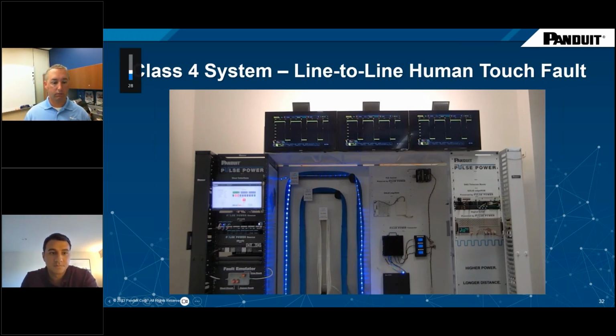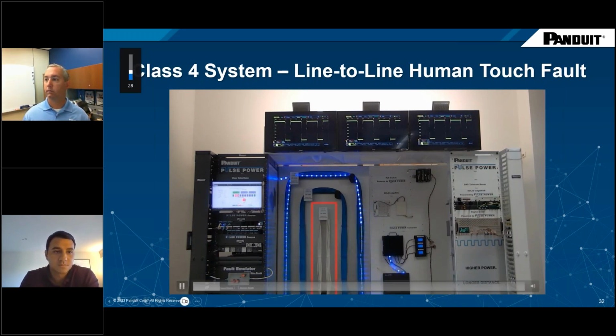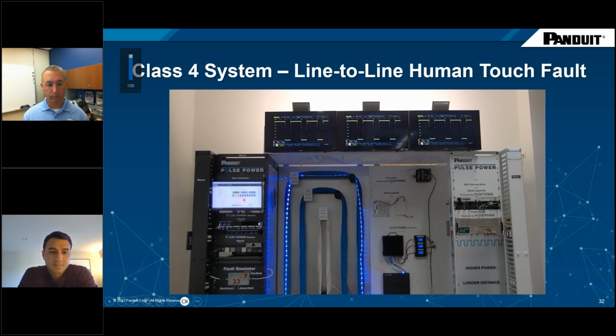You are looking at a demo of a Class 4 system. On the left, you have the transmitter, or source, delivering pulse current through the white cable in the center to the receiver, or converter, on the right. The white cable is a single pair of 18-gauge cable. The converter is powering various loads, one of which is the 3 floodlights above the TV, which are directly fed 48-volt DC from the converter. The TVs are showing you the shape of pulse current flowing through the white cable in the center.